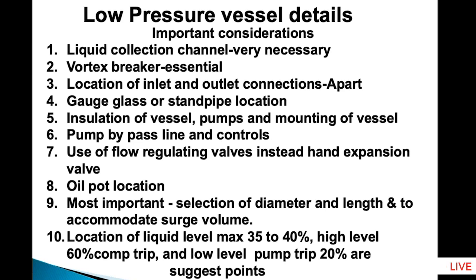What happens when your plant stops suddenly? The liquid in the air coolers will flow back to your LP vessel, and the LP vessel should be able to accommodate this surge volume, and therefore the diameter selection of the LP vessel is very important. The maximum liquid level to be provided is 35 to 40%, not more than that.